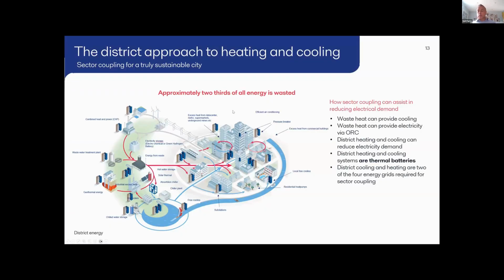So you may have noticed I mentioned district energy a lot rather than district heating or cooling. And that's because we need to think, as I mentioned earlier, of energy in a much wider way. And what we should see are two energy grids in terms of district grids, district heating and district cooling, feeding into the city. You then have a variety of sources that are utilized because the district system is completely agnostic of the energy sources. And then you're providing via substations in the buildings the heating or cooling into those buildings.